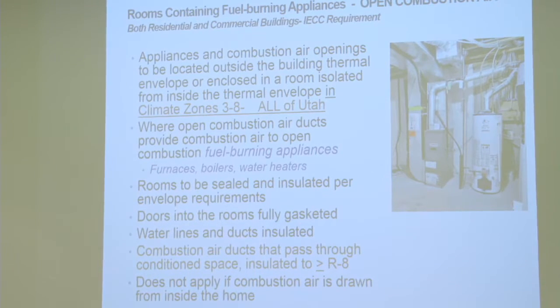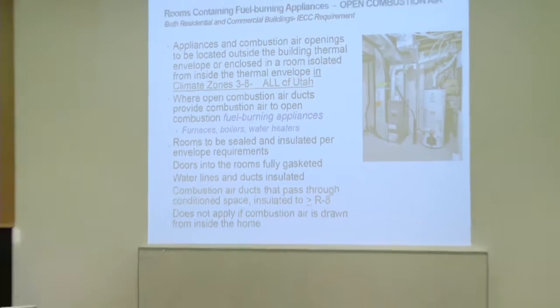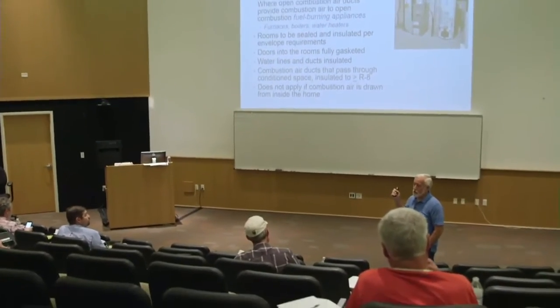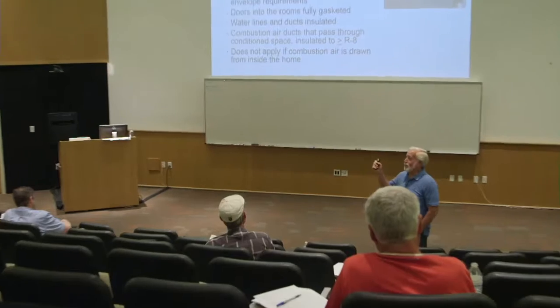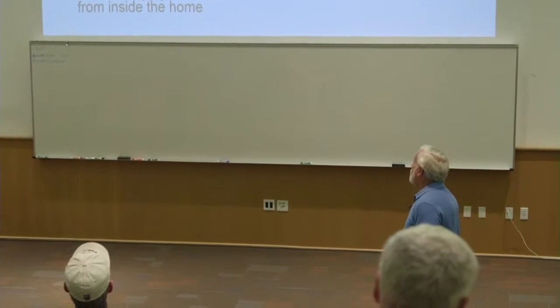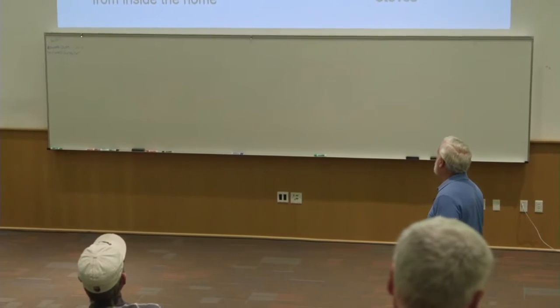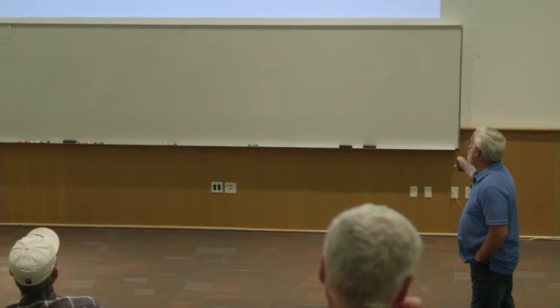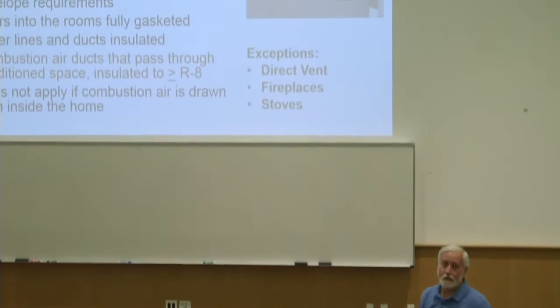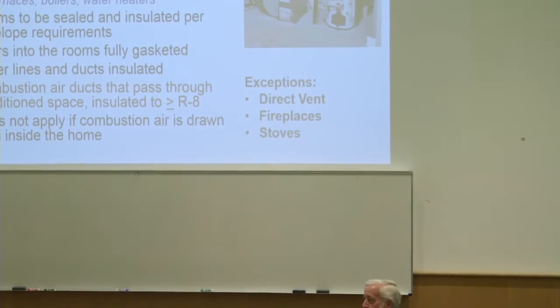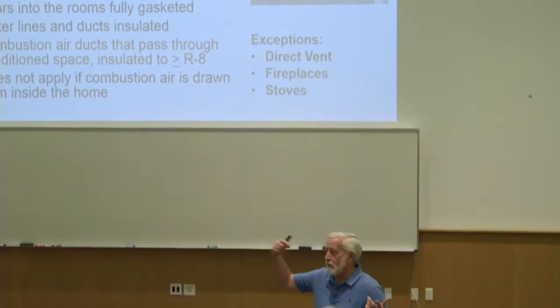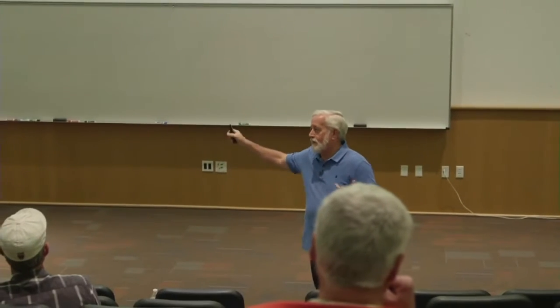You might be able to get away with drawing combustion air from inside the house on a water heater if you go to the fuel gas code and do the calculation. But you've got to do a blower door test to know how leaky the house is to do that calculation. Exception, direct vent. Everybody know what direct vent is? A pipe in and a pipe out. The flame never sees the interior environment of the house.